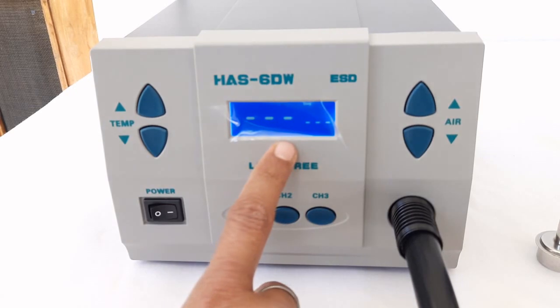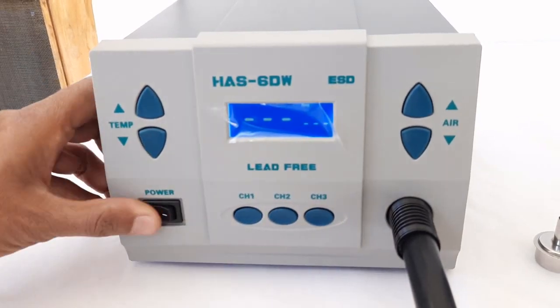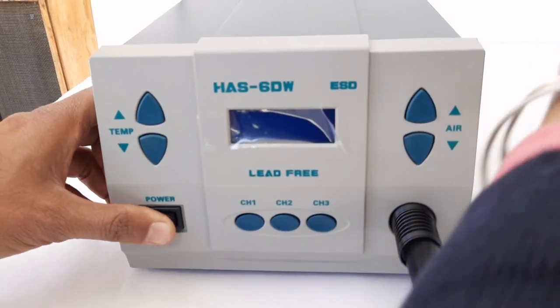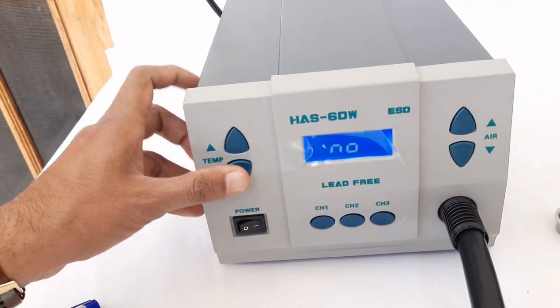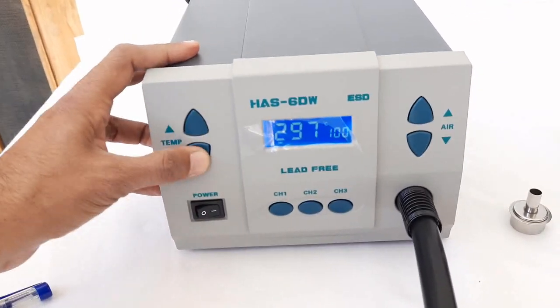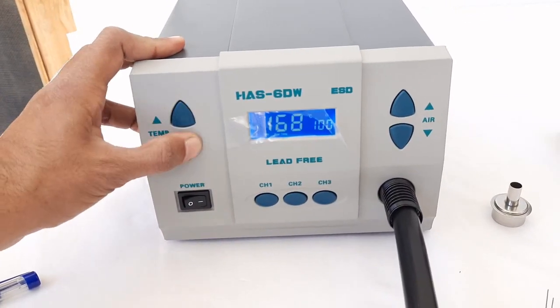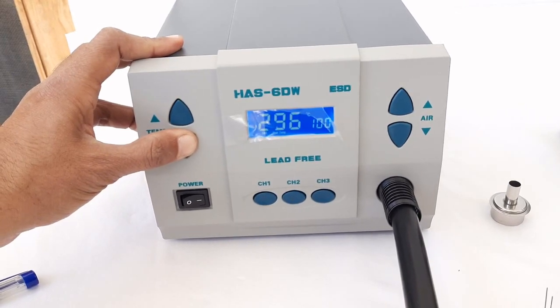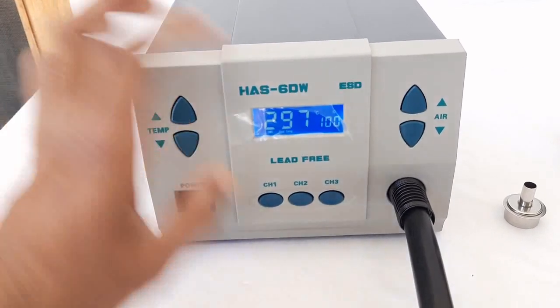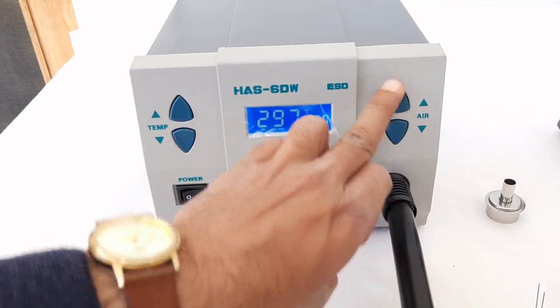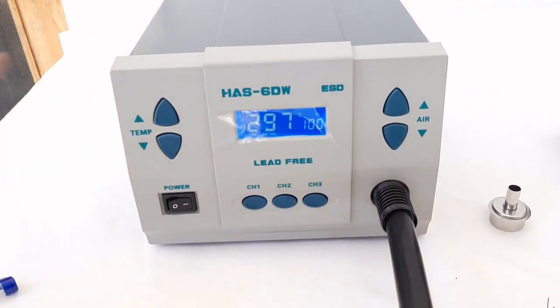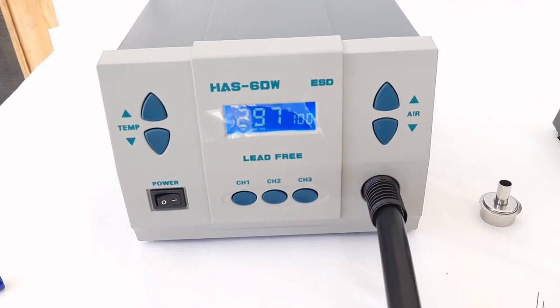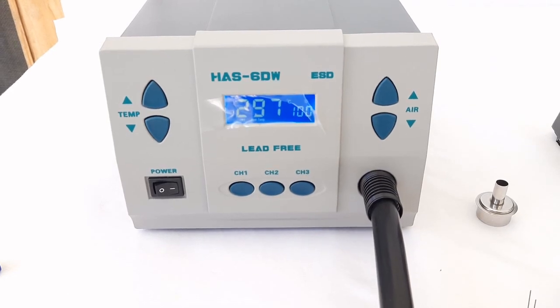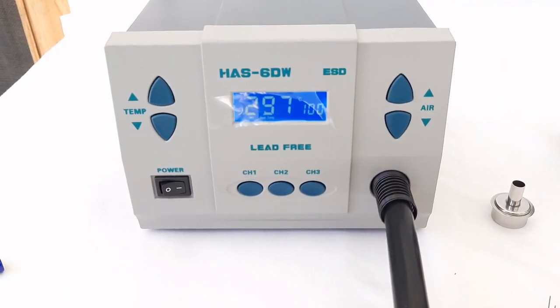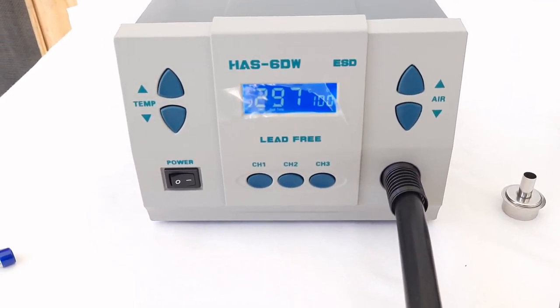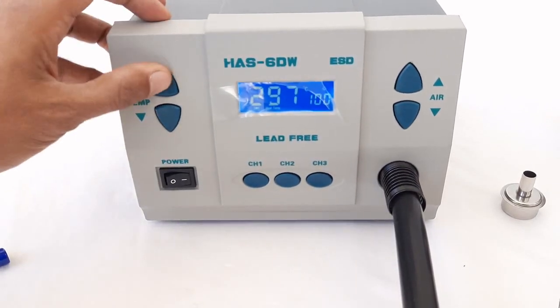And once we switch the unit off and then switch it on, we can see that we cannot change the temperature. Temperature has been locked, and similarly we cannot change the hot air flow. So the temperature and hot air flow have been locked at a certain level, and without changing the password or without inputting the password, we cannot change the temperature or hot air reading.